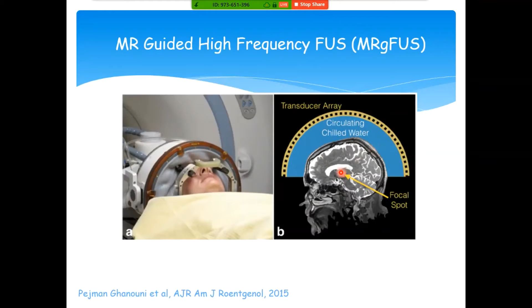So one of the major challenges in neuromodulation with focused ultrasound, which wasn't there with other utilities of focused ultrasound in different areas of the body, is actually the skull. The skull is a major barrier for the ultrasound wave, but they found a way to overcome this problem. We measure the skull here, and we know how to make sure that the ultrasound wave that gets into the specific spot will be synchronized with other waves that come from other transducers. So we change the angle of each transducer, and we also change the timing of each transducer, so the net effect will be maximized.